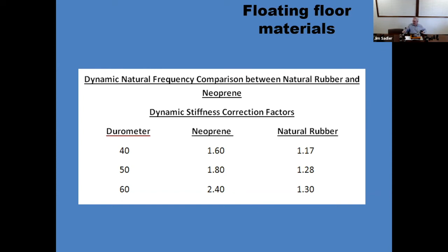Those values are higher for neoprene than natural rubber. So we realize a lower natural frequency with natural rubber than neoprene because of the lower dynamic correction factors. With neoprene at 6.7 millimeter deflection with a 40 durometer, which measures the hardness, the neoprene has a natural frequency of 7.2 hertz. The natural rubber goes down to 6.2. At 60, it goes from 8.9 down to 6.5. So the natural rubber provides a better isolation material than the older neoprene. Just a recent upgrade.